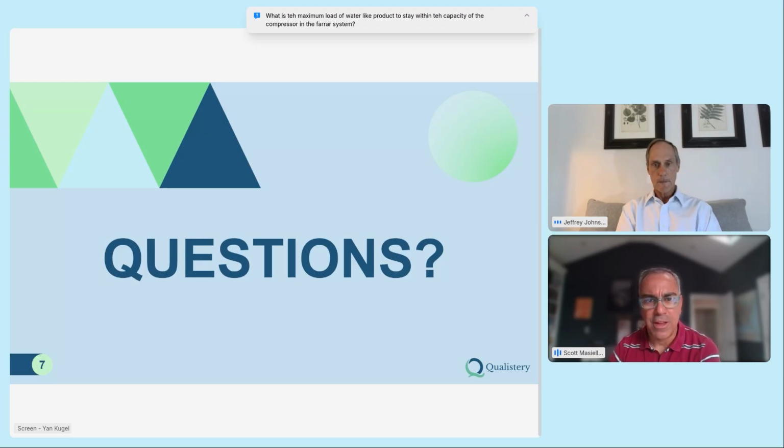The only thing I would say is, as you were explaining it, Jeff, the one thing I wonder is when you talked about it may warm up to -60. So the air, when we set the FARRAR unit on blast, the unit is running at -80 and is moving air at 1 air change a second through the system. When you have that much material in there, the air on its return path is not going to be -80. It's going to be probably in the -60 range, at least until the bottles get to -60, and then it'll start to cool down from there.